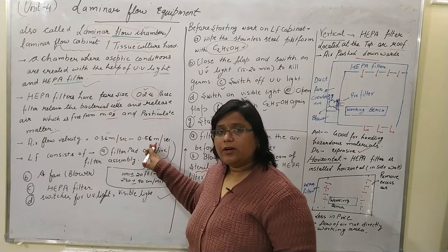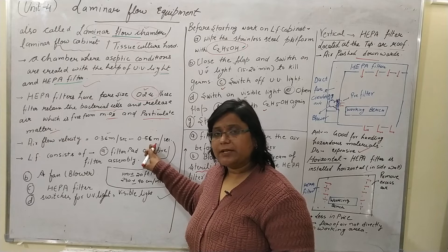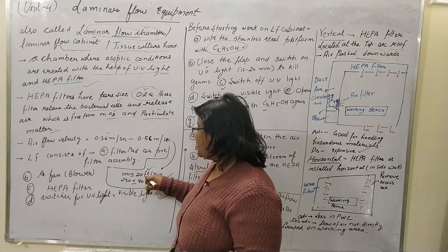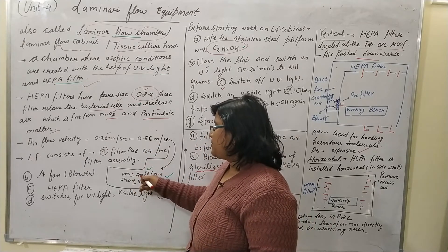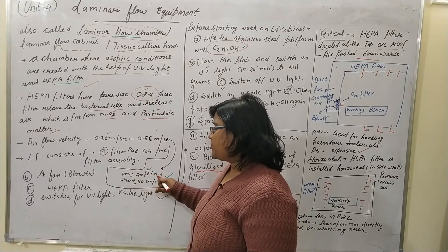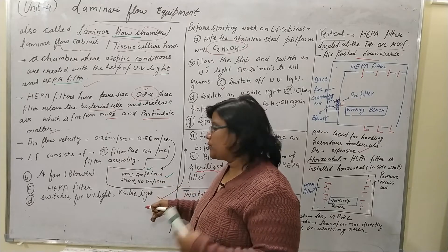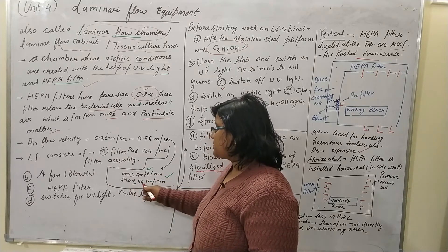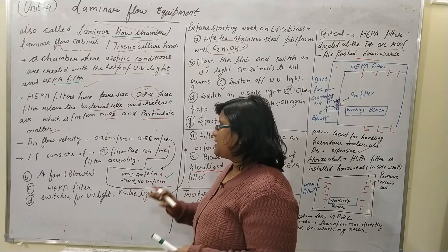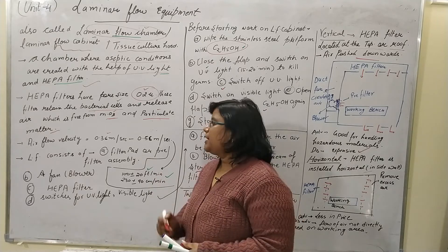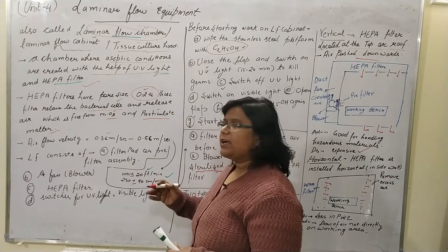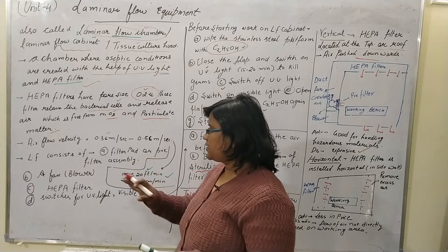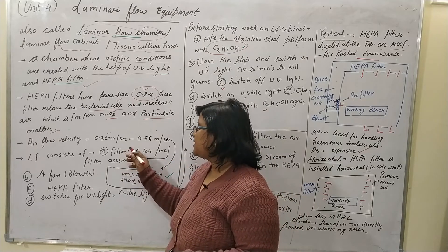The airflow velocity is 0.36 to 0.56 meters per second, or 100 ± 20 feet per minute, or 230 ± 90 centimeters per minute. The laminar airflow cabinet has some basic installations: a filter pad or pre-filter assembly, a fan or blower, the HEPA filter, and switches for UV light, visible light, and the blower.